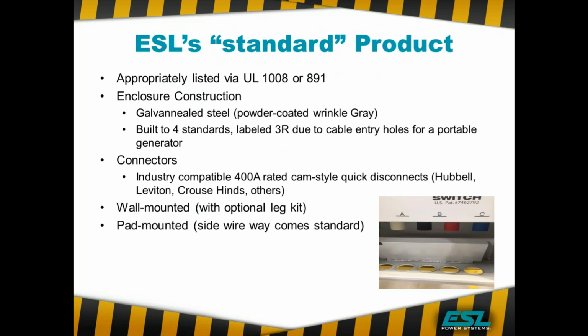Let's look at our standard product. So all the stuff we're going to talk about, our storm switch, our triple switch, they're all going to fit within this category. Again, properly listed for the application. Our standard units are galvanneal steel, powder coated, wrinkle gray. They're built to a NEMA 4 standard and labeled NEMA 3R due to these holes that are down here at the bottom, which allow the cables from the generator to connect to the transfer switch or docking station. So once you're connected, obviously you're not watertight. So when it's not in use, it pretty much meets NEMA 4 standard, but it's labeled NEMA 3R.